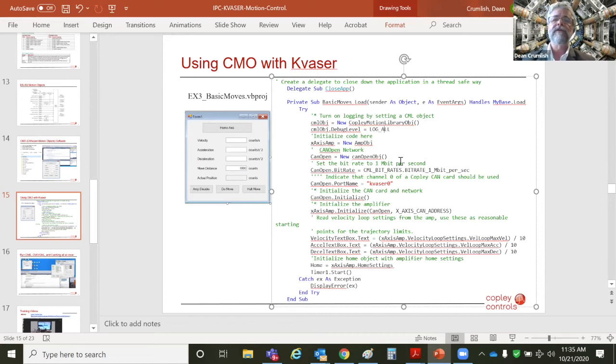So using that CANKing, you could create another log to confirm if there are other messages generated on the network. You create a CAN object, and once you create it, you can set a bit rate. This one's 1 megabit, which is the drive default. And the CAN port is Kvaser 0. If you had a 2-channel CAN card, you'd have a Kvaser 0 and a Kvaser 1.